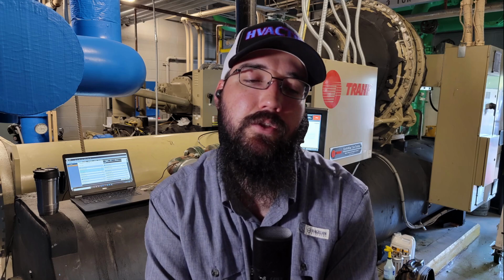So with that calibration, if the motor can rotate at all and that valve is changing position at all, chances are your stator is okay. That's not your main issue. Then if the motor itself is not the issue, we have to start looking at the mechanical aspects. And in that calibration process, did the valve hit its end stops? Was it even able to move far enough to do that? I alluded to this earlier. That's one of the ways that I've caught mechanical failures like this before.